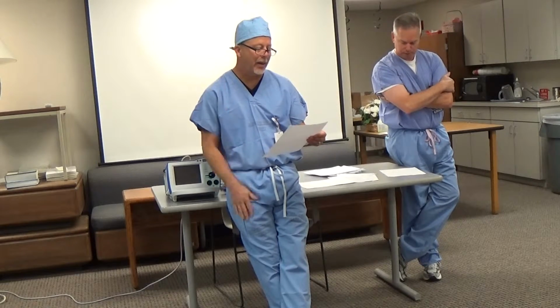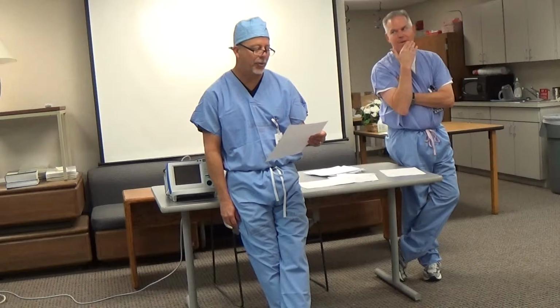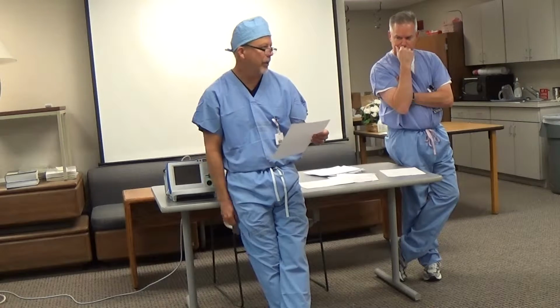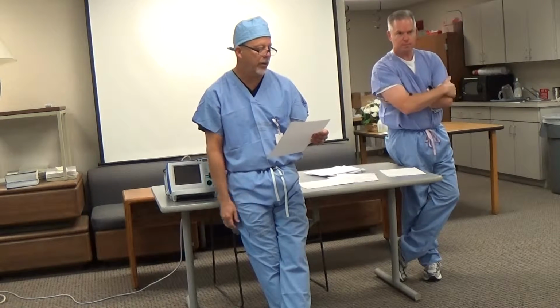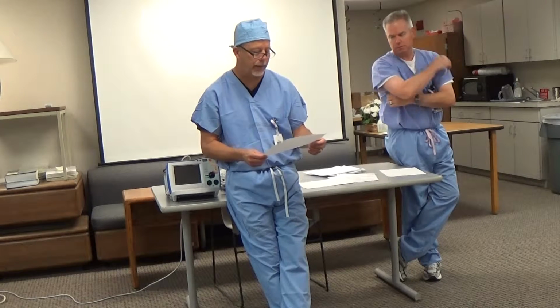And when they get the pads in, we put the pads on. Pads go where? Front, back, transthoracic. We turn the voltage up to where we capture, and then we start playing with it there. We turn the rate up to, like Joe said, most of the time 70 is a good place.